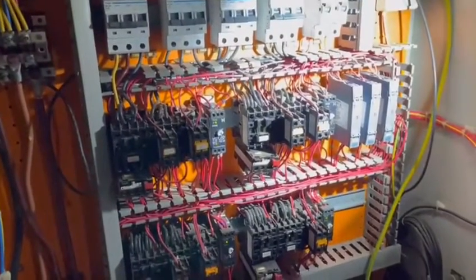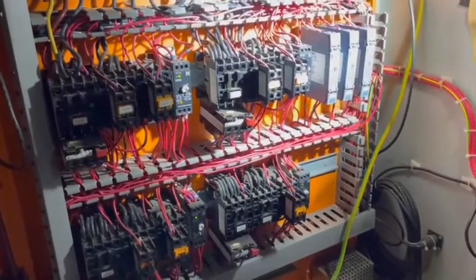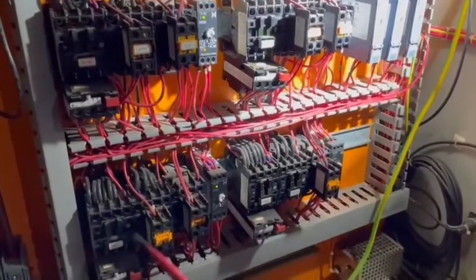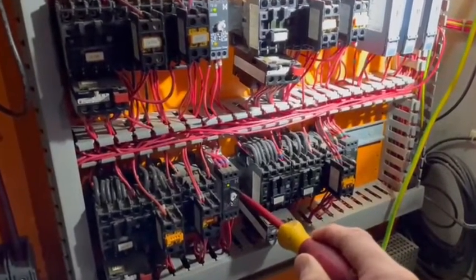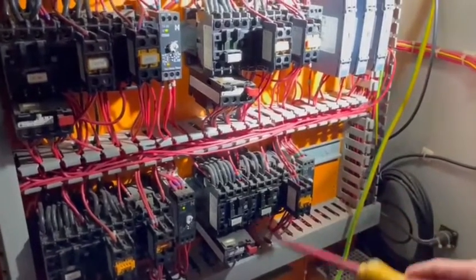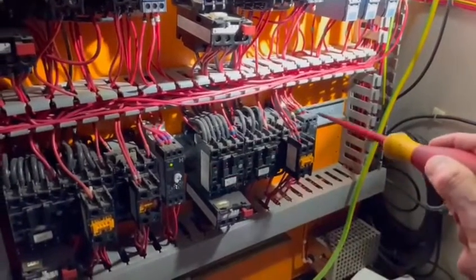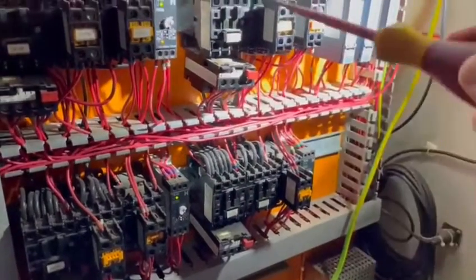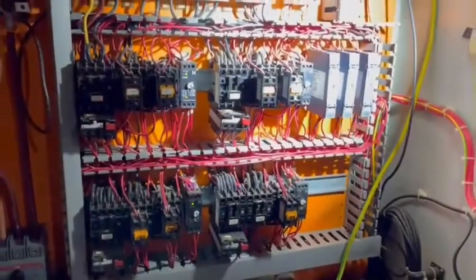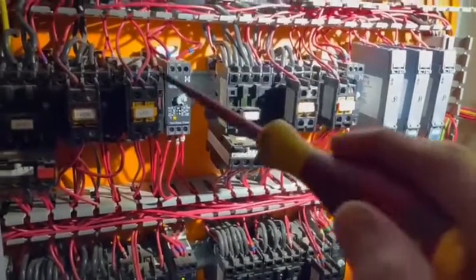So technically all four motors would now be running. I'll just undo that, and that will lock that one out as well, because there's a fault on this one — we're thinking it's probably the time switch. By manually letting go of that, it will also drop the fourth one out. We're going to talk to the farmer and see what they need to do — we might just change this one over so at least the first three fans will work.